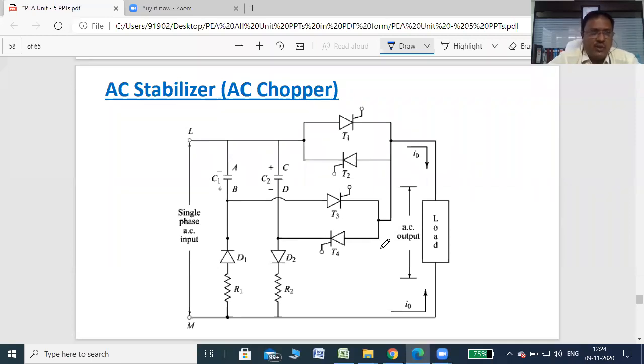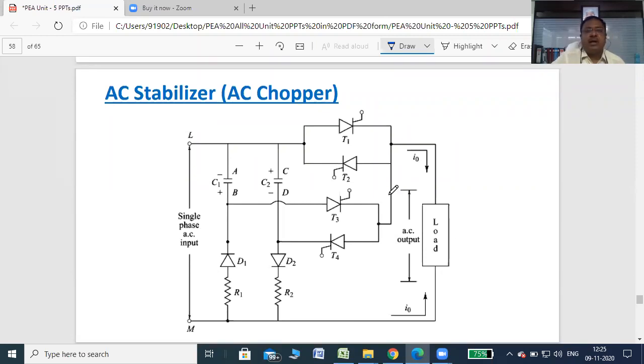In it the triac is used so that both the positive and negative parts of the cycle can be controlled. In this circuit diagram, in place of a triac, only SCRs are used because SCRs are more reliable than triac for controlling, so anti-parallel SCRs are connected here in the circuit. So that will work like a triac.